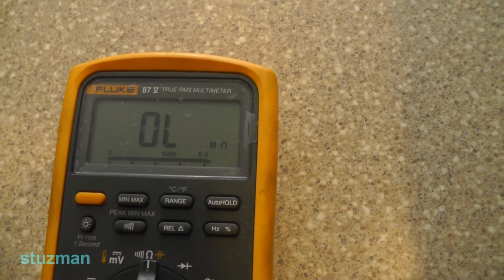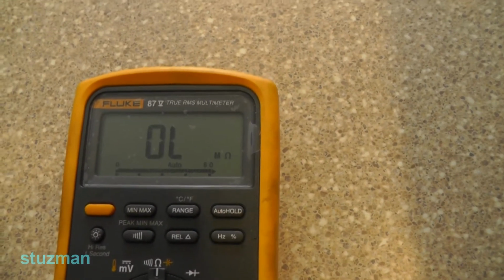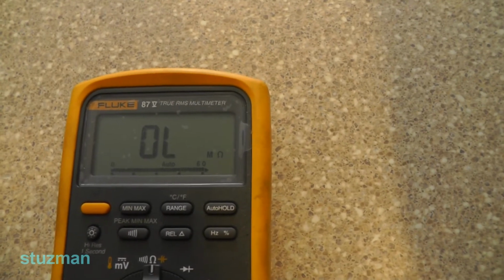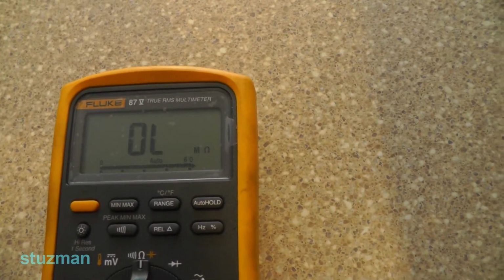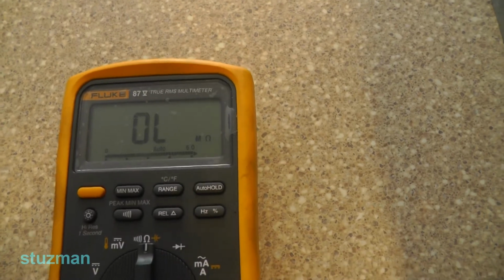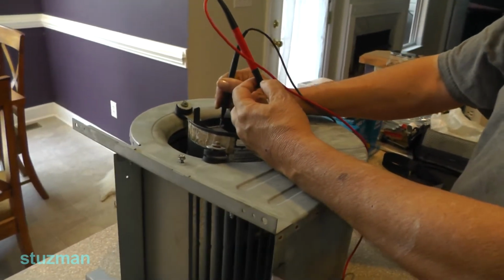OL, you can't get better than that. So it shows no leakage resistance from the winding to the frame. Anything over 100,000 ohms, you can look at that as being good, but the higher, the better, okay? If you got something that's under 100,000, then the motor's going to be bad, all right?